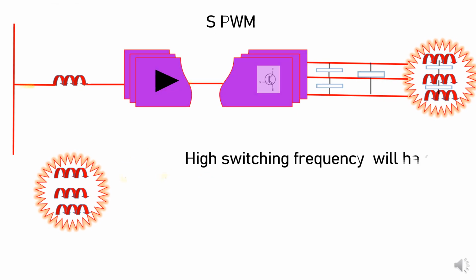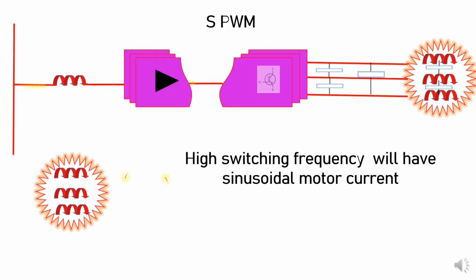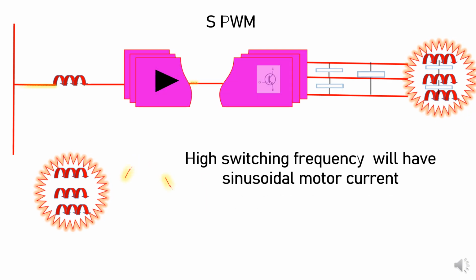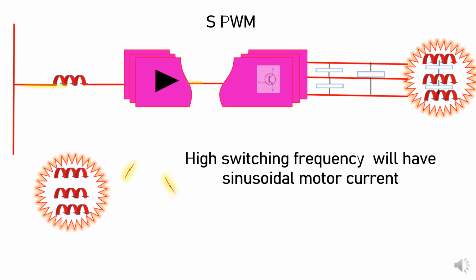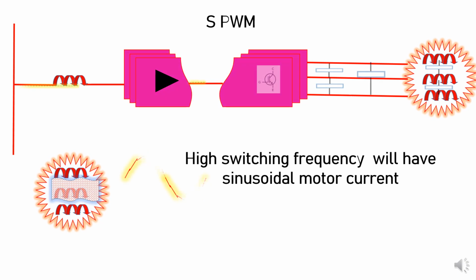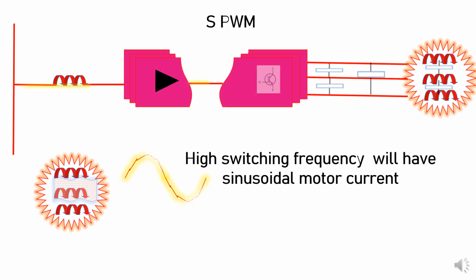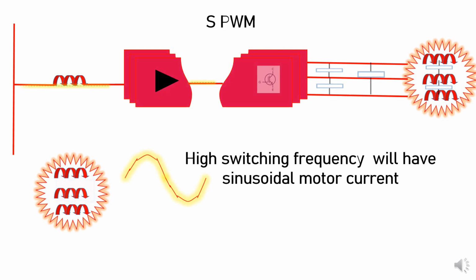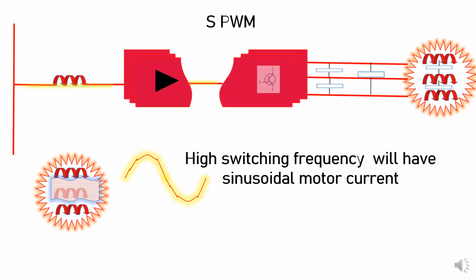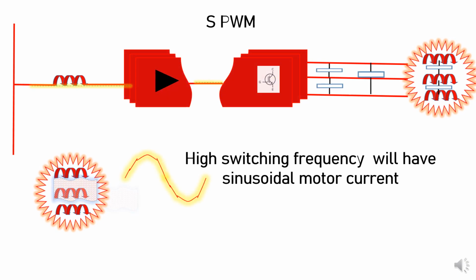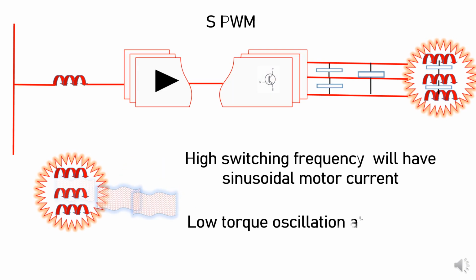The second one is that a high switching frequency gives a waveform nearer to the pure sine wave. So this is the advantage. Lower switching frequency will generate less heat. If you keep the higher switching frequency, you will get a sine wave nearer to the motor requirement. So these are the two extreme advantages of lower and higher switching frequency.